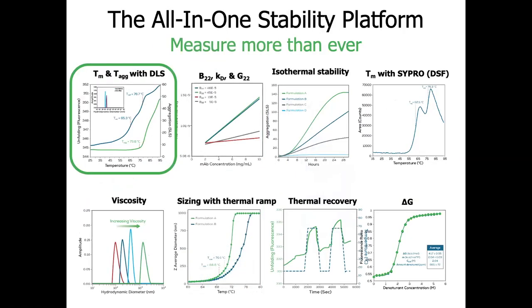Because of the three detection methods inside of the UNCLE, there are many different applications that can be run in this one instrument. Tm & Tagg with DLS is our most popular application. Essentially, it looks at the unfolding temperature as you thermal ramp the samples — the TMs — and the aggregation temperature, or the onset of aggregation, which is Tagg. Additionally, it looks at dynamic light scattering information at the initial temperature and the final temperature.